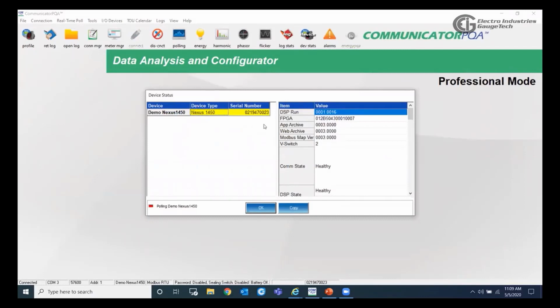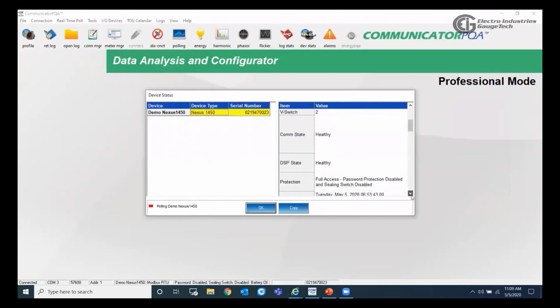On the device status window, on the left side, we will be looking at device, which is the meter's name. This is something we can configure on the profile. We will talk about this later. And then we have the device type, which is the model, and the serial number. On the right side, we will see the firmware information, like the version of the firmware, and the V switch of the meter. And it tells us about the status of the meter. You can see here it has a healthy COM state, healthy DSP state, and the password is disabled.